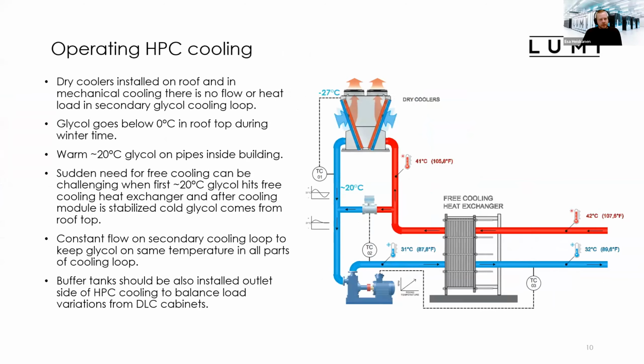So then about the HPC cooling, we have these dry coolers installed on top of the roof, and we have over 40 meters or more, maybe in total 50 meters of pipeline from these free cooling heat exchangers to the chillers, and those pipes are running inside the building, so the building is heated, so temperatures in these pipelines are approximately 20 degrees. But when we are running in fully mechanical cooling, we have no flow in this cooling loop. So it can end up on the coldest days that we have -20 up to -27 degrees cold glycol waiting outside and 20 Celsius glycol inside the pipeline before the heat exchanger.